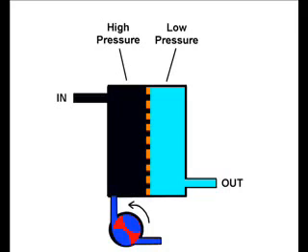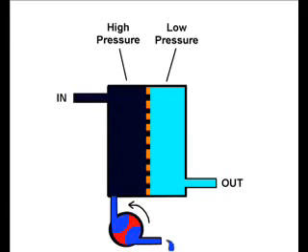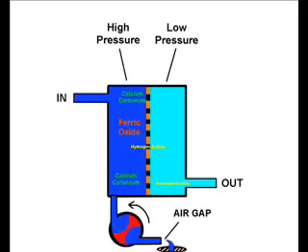We need some way of getting this brine out of the high pressure side else we would eventually clog and foul the membrane. This is often done by a valve or some sort of a weep. This little valve rotates and holds that differential pressure for a period of time. If we need that differential pressure to be maintained in order to push the water through, we hold it and then we dump it. And as we do this, we repeat the process. We dump out that concentrated water that has those contaminants in it. And in this way, the free floating contaminants are washed out.